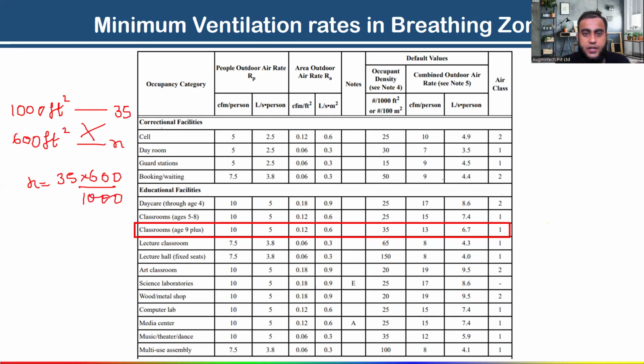Tell me, has anyone done it? Near about 1 minute, 35 into... Yeah, right. Total. So in our case, how many people do we have? 21. So in this way you have to calculate the number of people, CFM per person, and CFM per square feet value. Now I hope all of you are clear on this.